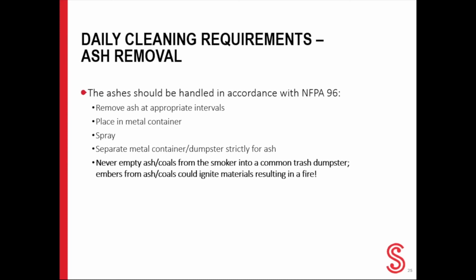Once the wood and ash have been sprayed, place them in a heavy gauge container with a tight-fitting metal lid. We're looking for a minimum of a 16-gauge metal with a capacity not to exceed 20 gallons. This container must be used for this one purpose and must be able to be handled easily by an employee assigned to the task and must pass easily through any passageway to the outside of the building. The container should always be covered when it is being moved through the premise. When any holes occur in the container from corrosion or damage, the container should be repaired or replaced immediately.